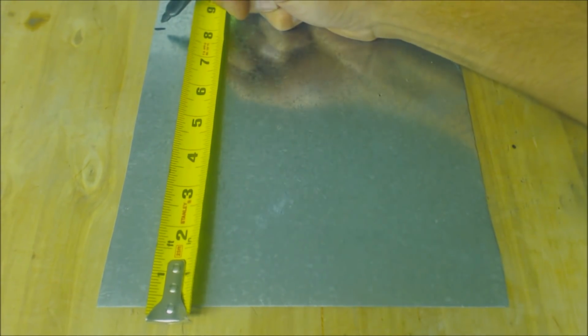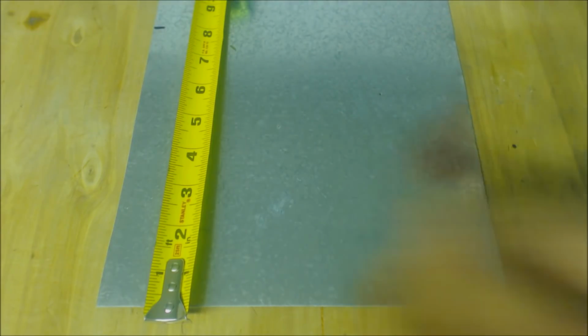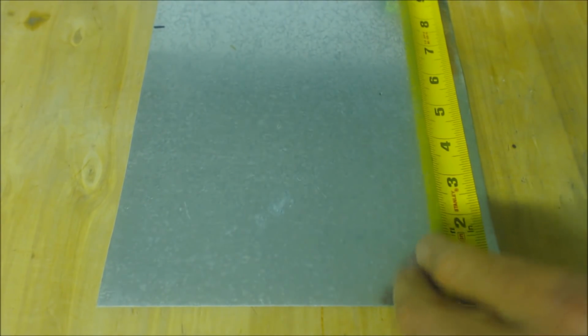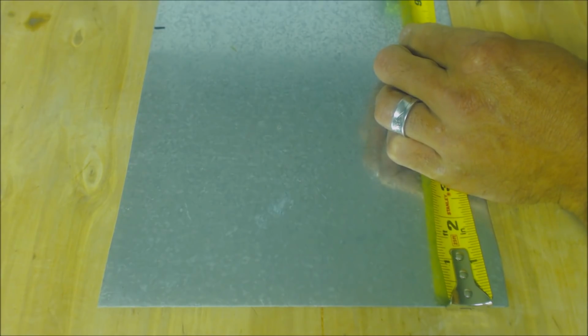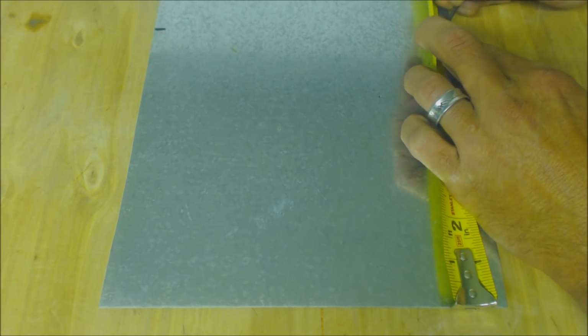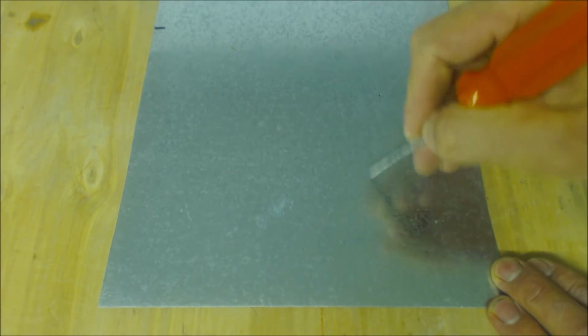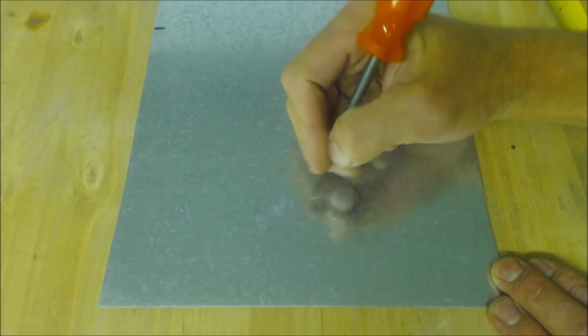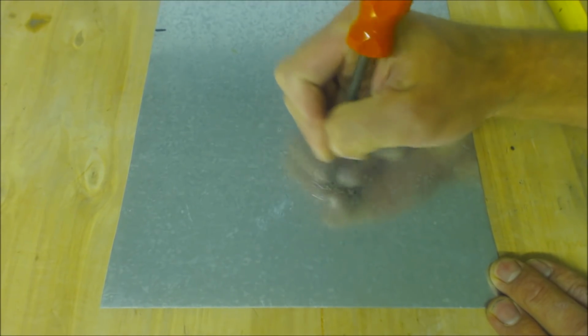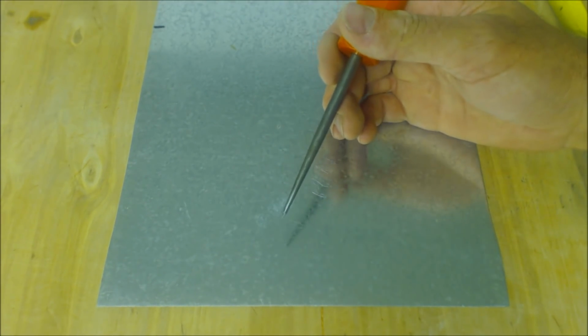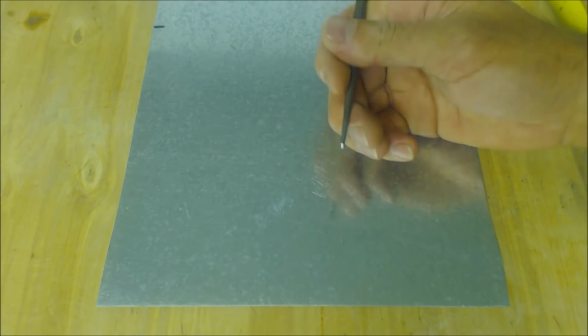Now, if we wanted to make a less intrusive line, we can use a scratch-awl. We need to make two marks to form a line straight across, so we're going to use the scratch-awl to mark at 8 inches. There's our mark right here, a little harder to see. What I typically do when I scratch like that is make a little tail in order to find it. But make sure you're not using a scratch-awl to mark ductwork if you're making a condensate pan, because you're scratching through the galvanic coating on the ductwork. You can use a scribe instead.